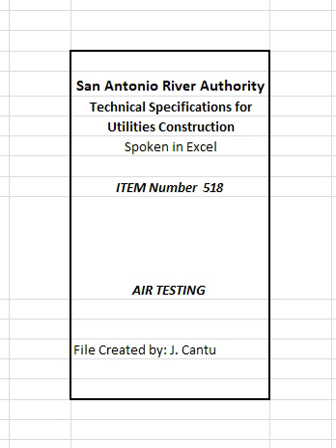before the test. Manholes are to be plugged so they are isolated from the pipe and cannot be included in the test. Under no circumstances is one section of pipe or material, i.e. ductile iron pipe, to be tested with another pipe section or material, i.e. PVC pipe, at the same time.